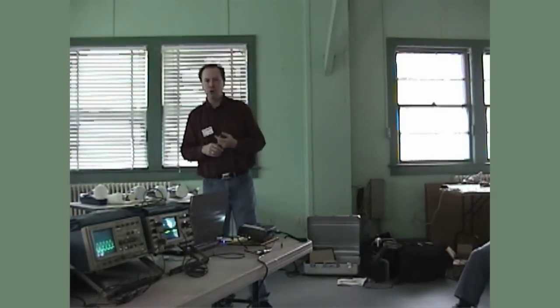Well, it's a good question. Most digitizing scopes use an 8-bit A to D converter, which means any voltage coming in is sampled, so the voltage you see vertically is one of 256 values. Now 256 values spread over 3 or 4 inches, you really can't see the stair step, and the traces will generally connect the dots, so you generally don't see the effects of the digitizing.